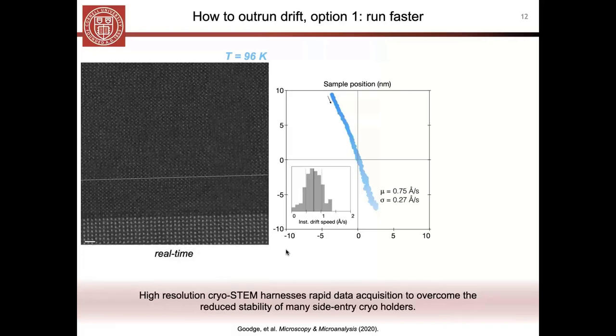We can actually quantify the amount of this drift by tracking the sample position over a long time, in this case just over 4 minutes. You can see the very directional nature of this drift - that's the direction of the rod and the direction of thermal drift in this particular acquisition. We can extract a mean instantaneous velocity here, which is about 3/4 of an angstrom per second. That's the kind of drift speed we're up against under a lot of these in situ cryogenic conditions.